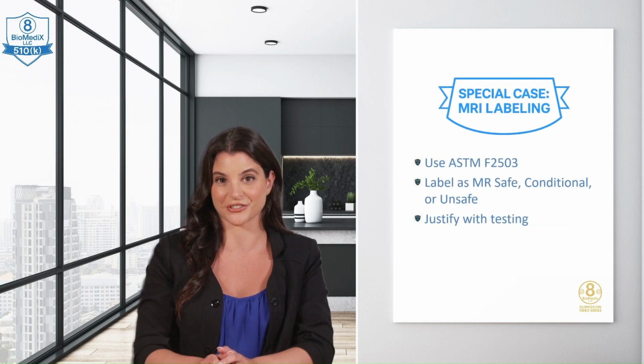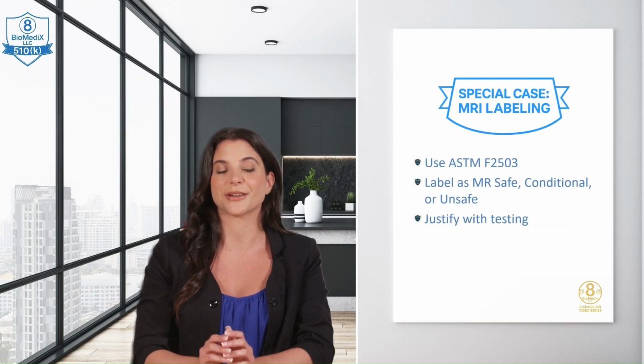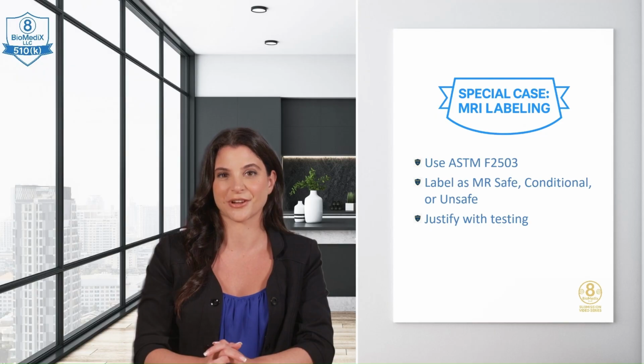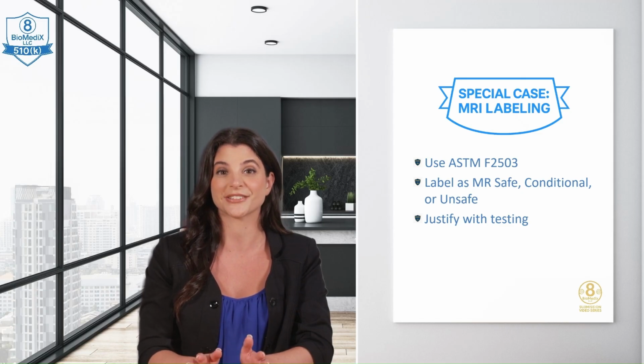If your device will be used in an MRI environment, test and label according to ASTM F2503, whether it's MR safe, conditional, or unsafe.